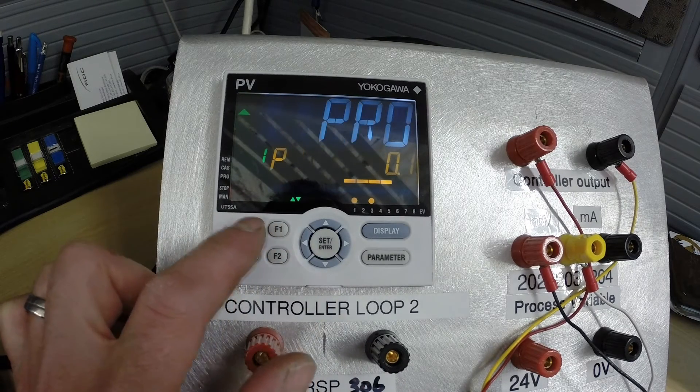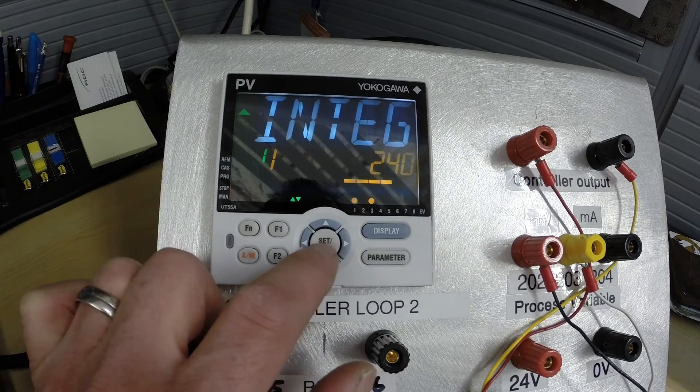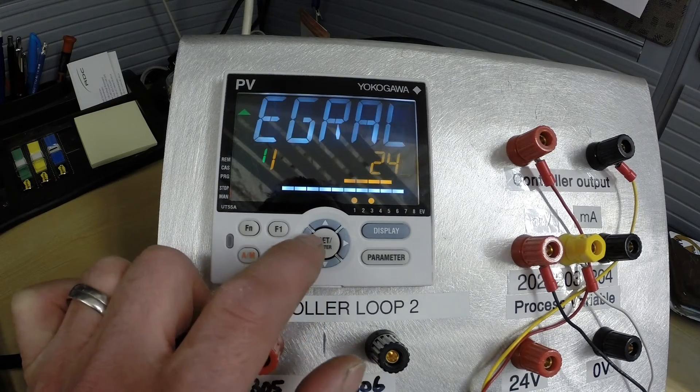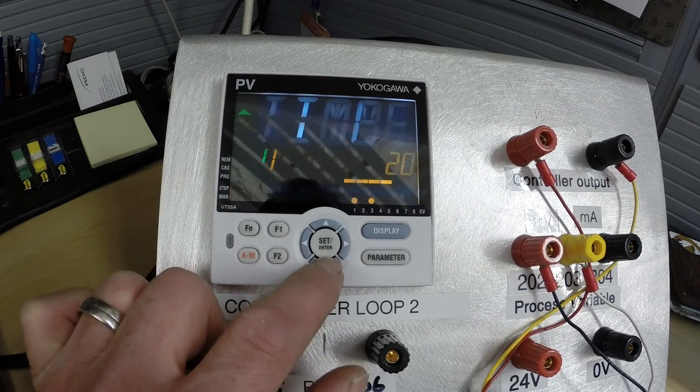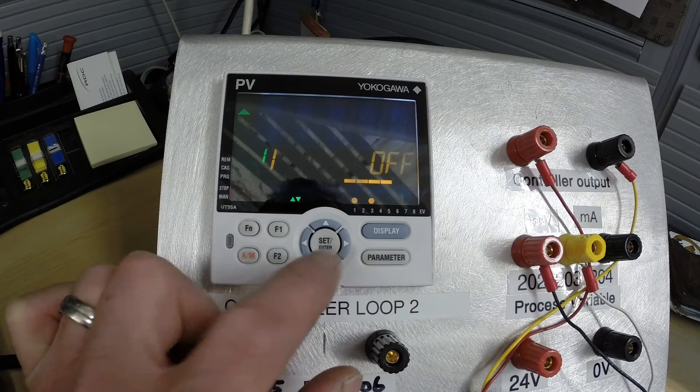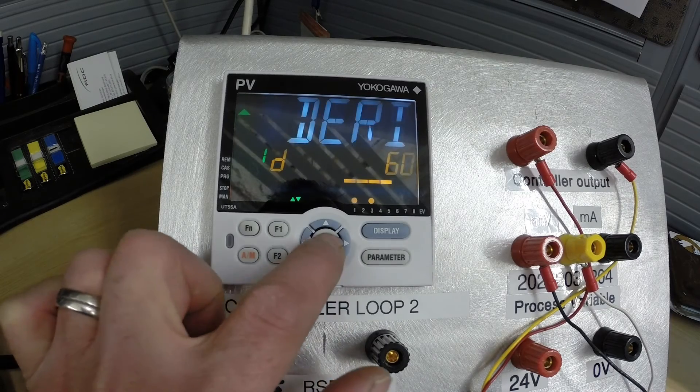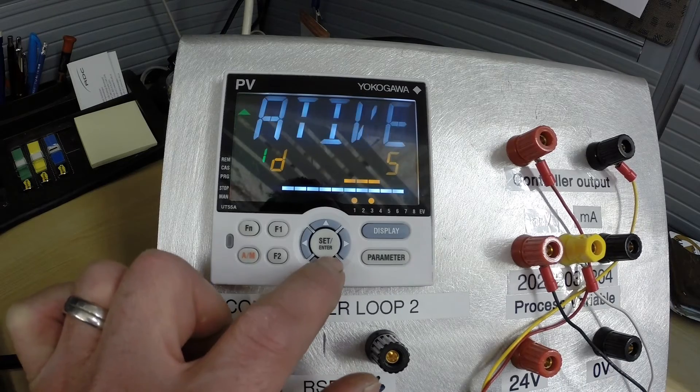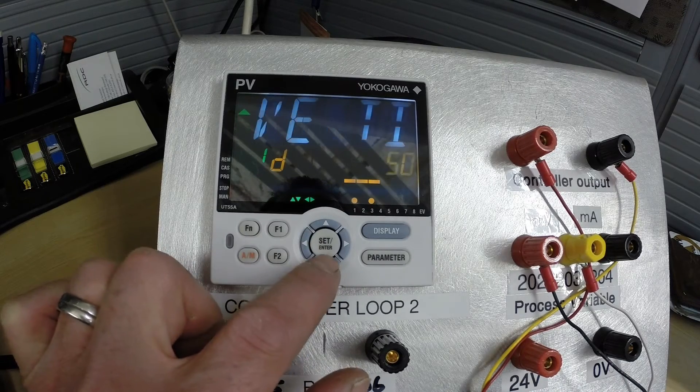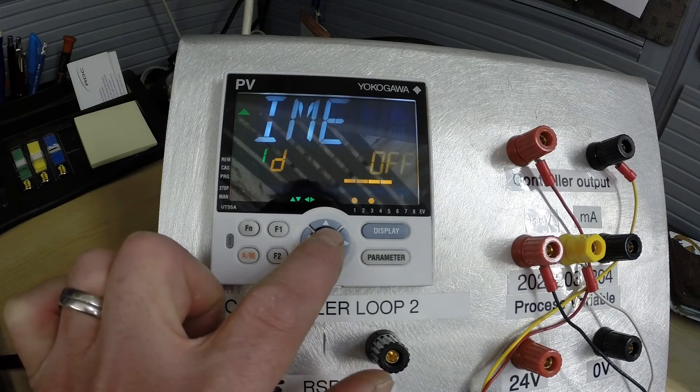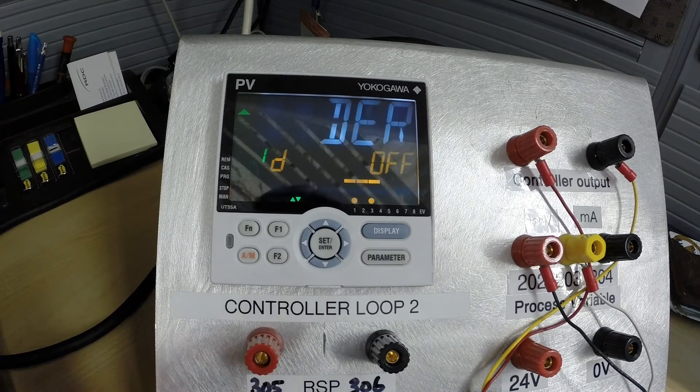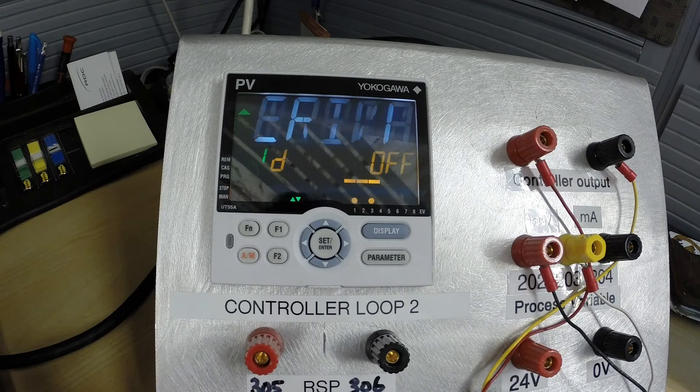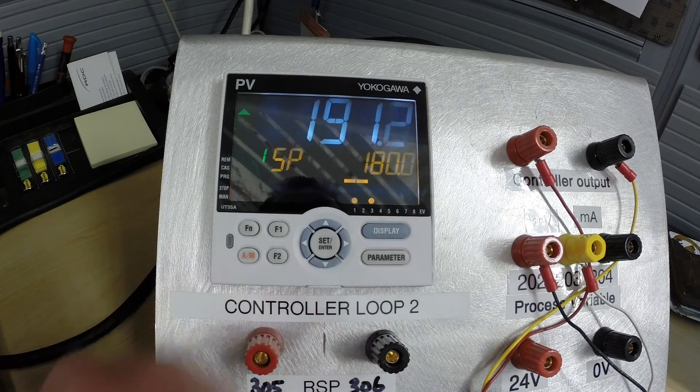And to make things simple we're going to turn off the integral and derivative functions. So press set to accept that. Function again. Scroll down to get our integral value. We're going to change that and I'll go over to 200 here to make it quicker. And you will see we can select off, so we will do that. We will go down and do the same for derivative. If I go to the 10 spot I can go much quicker. So there we are, off. So that is our PID settings as we have it right there.